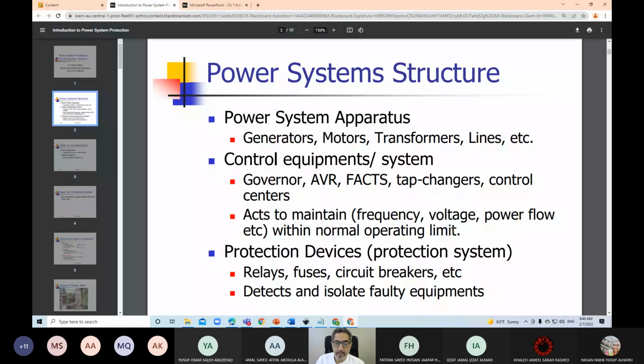So this is the purpose of the protection system: by using fuses, circuit breakers and relays to detect these abnormal conditions and initiate the action to disconnect the faulty components. So its main purpose is to detect faults and abnormal conditions and isolate the faulty equipment from the system so that the system continues its operations, okay?